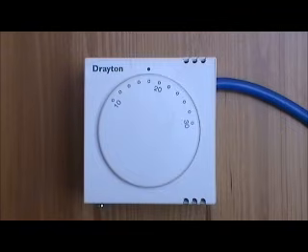Turning a room thermostat to a higher setting will not make the room heat up any faster. How quickly the room heats up depends on the design of the heating system, for example, the size of the boiler and the radiators, and the temperature that the boiler is going to increase the water flowing through the radiators to. Neither does the setting affect how quickly the room cools down.